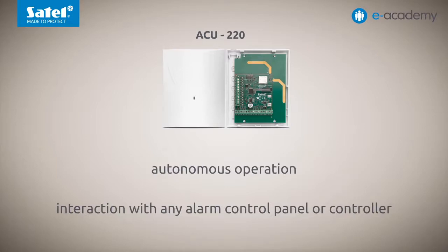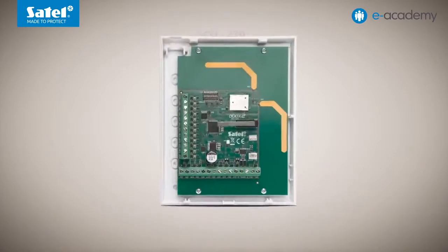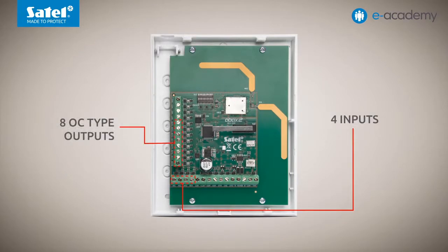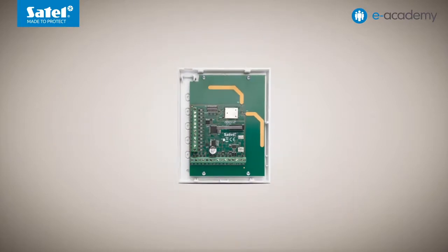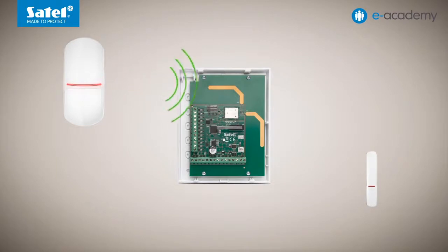The ACU220 serves as a universal module of wireless devices. In this case, the built-in programmable inputs and programmable outputs available on the controller's printed circuit board are used for interaction with the above-mentioned control panels, controllers and other devices. For the ACU220, the diversification of antennas is also worth mentioning. To keep the communication parameters as good as possible, the module will automatically select one of its antennas to receive transmissions, depending on the strength of the received signal.